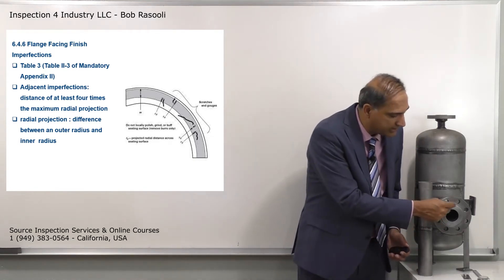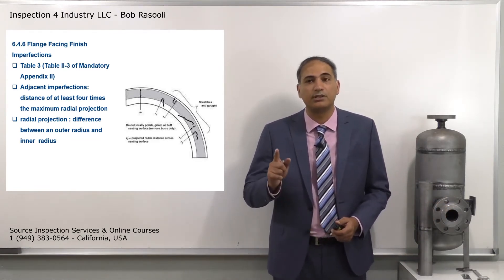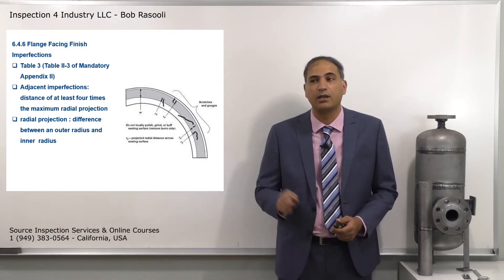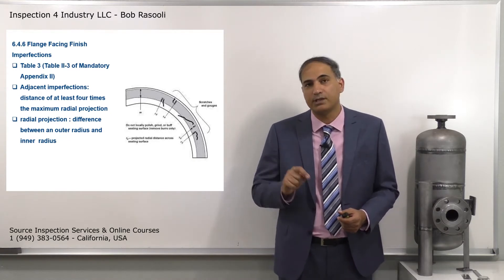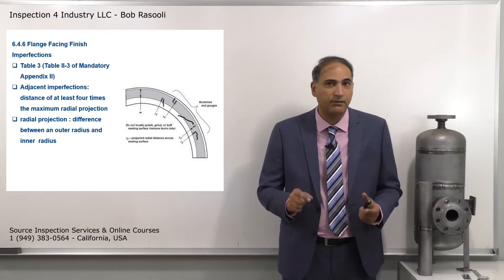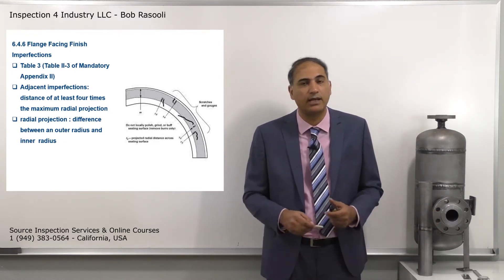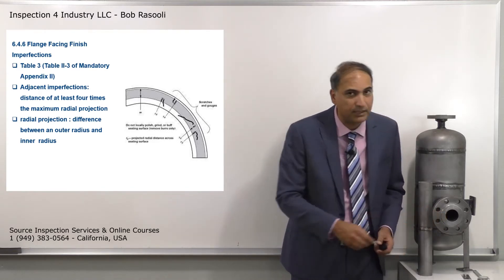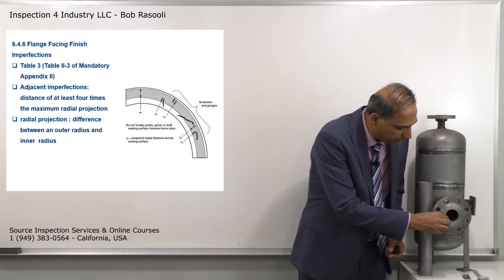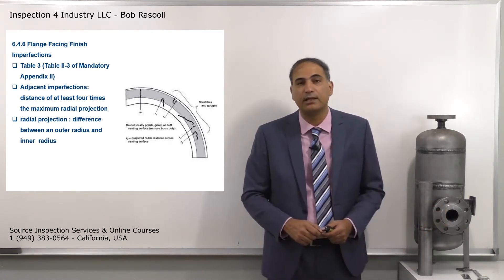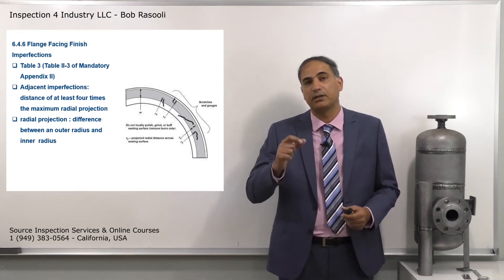When a cut goes through the serration perpendicularly, the inner to outer surface span gives a large radial projection. There's also an image on screen you can pause and focus on to see how this works. Cuts or scratches that pass through the serration get more radial projection, while cuts parallel to the serration give a much smaller radial projection and a more lenient acceptance criteria.